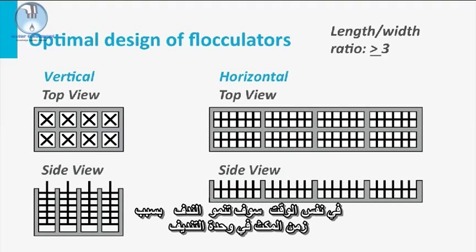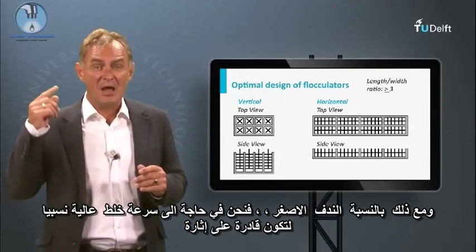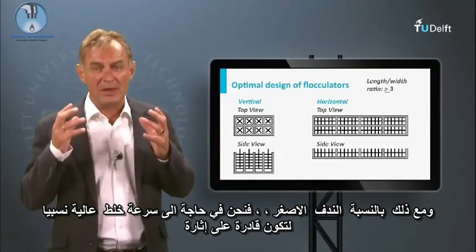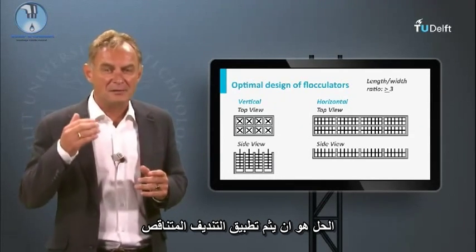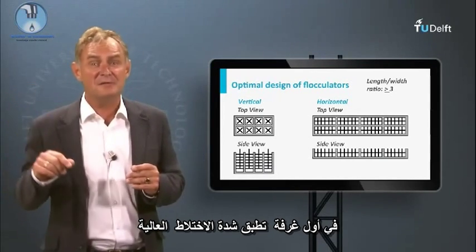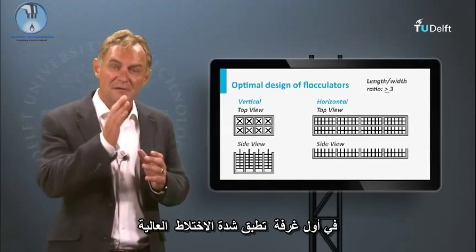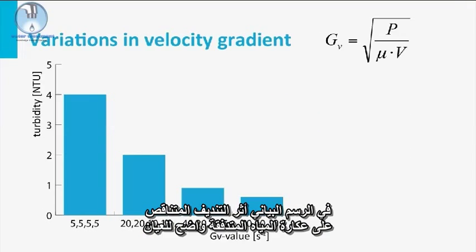In the meantime, the flocs will grow with their residence time in the flocculation unit. Larger flocs are more sensitive to floc break-up, so slow mixing is required. For smaller flocs, however, a relatively high mixing intensity is needed to provoke collision of the pin flocs. The solution is to apply tapered flocculation: in the first compartments, higher mixing intensities are applied and gradually the intensities are diminished. In the graph, the effect of tapered flocculation on effluent water turbidity is clearly visible.